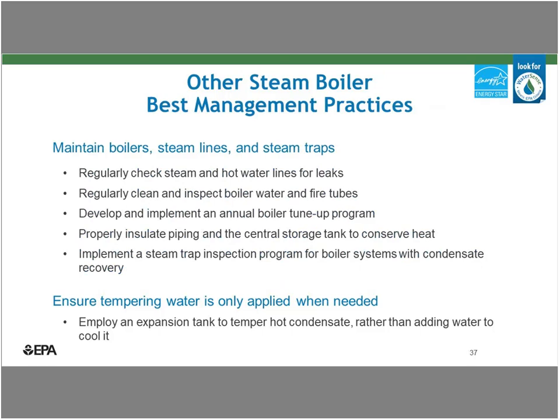Aside from installation of condensate recovery, the key to an efficient boiler operation is to really keep the components in good working order. So check your steam and water lines for leaks. Check to make sure that your steam traps are maintained and functioning properly. Regularly clean and inspect the boiler water and fire tubes for good heat transfer, and tune up your boiler for efficient firing, recommended on an annual basis. Make sure your steam lines and condensate return lines are properly insulated. That helps prevent heat loss.